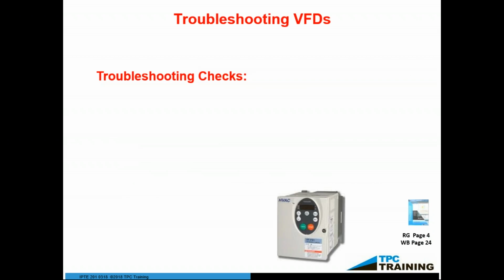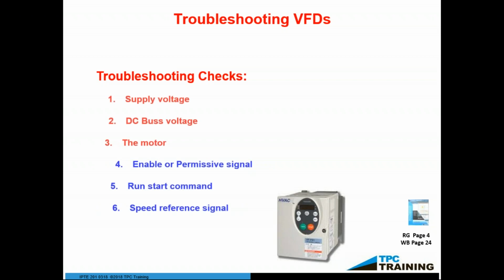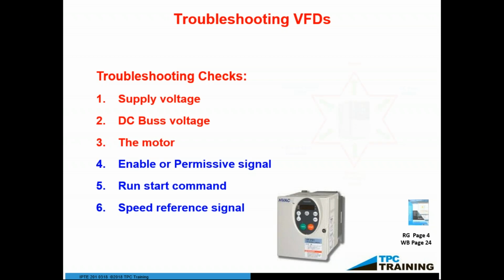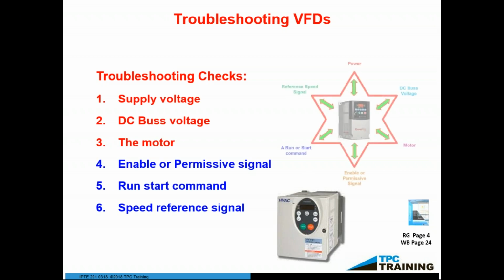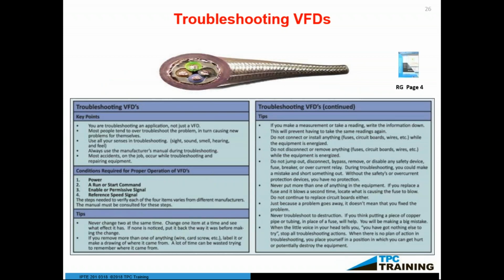Things to think about. Troubleshooting VFDs, troubleshooting checks. We would check supply voltage, bus voltage, DC bus voltage, the motor, enable or permissive signals, run or start commands, and speed reference signals. If you have all those 6 checks, you win, right? And we show you how to do it. We have this little VFD star thing that we talk about, but those 6 things matter. If you have that information, you could troubleshoot this VFD very simply, very easily.